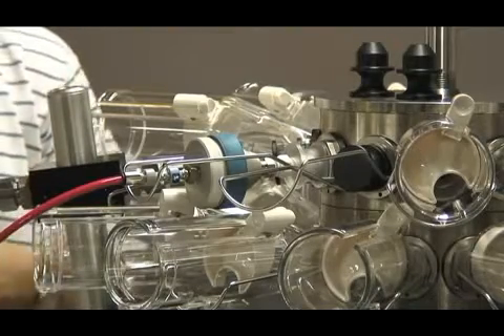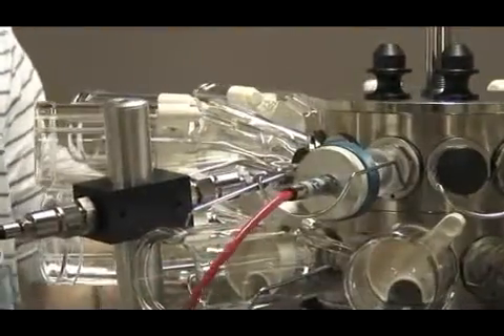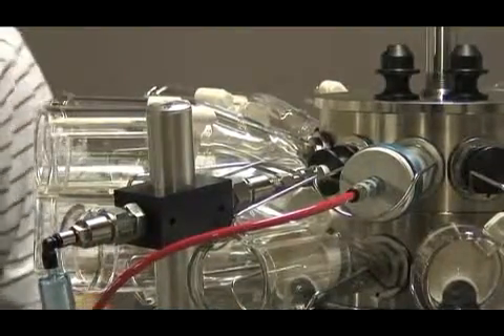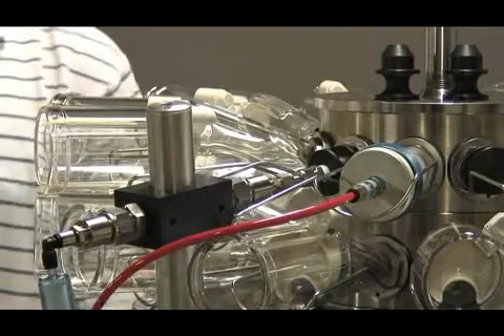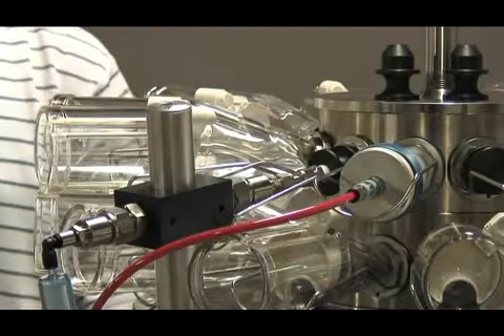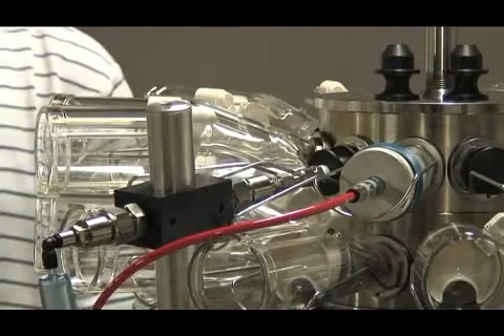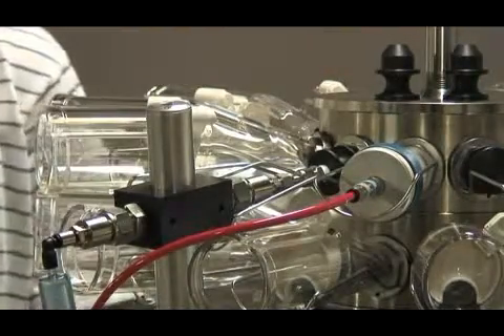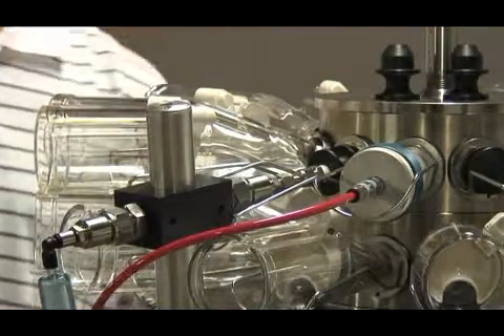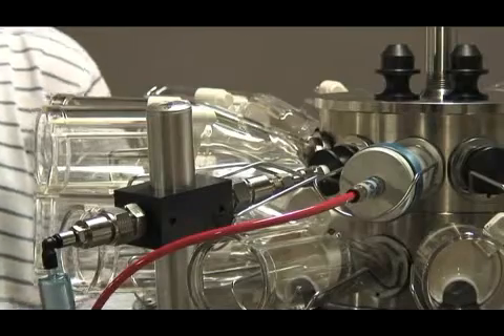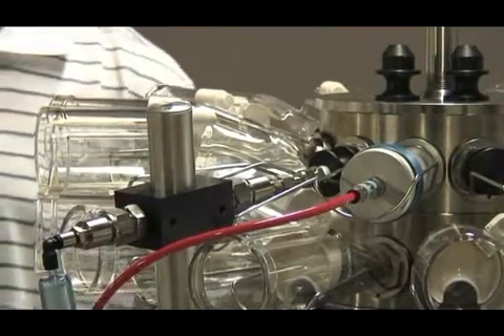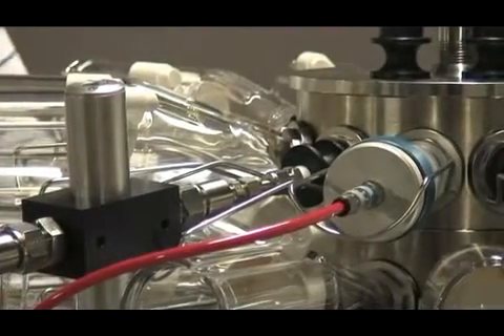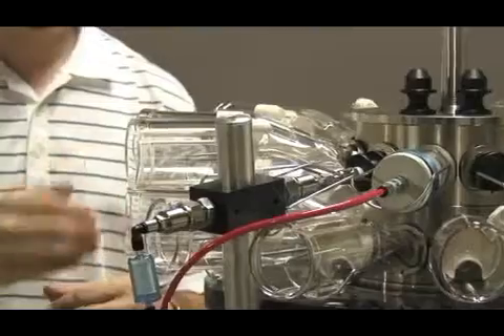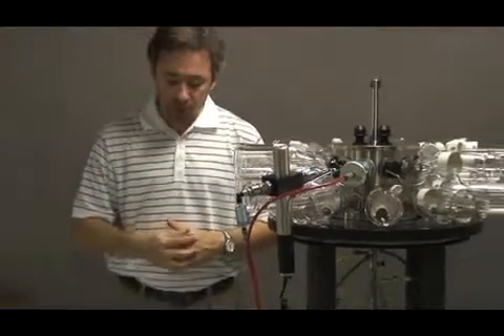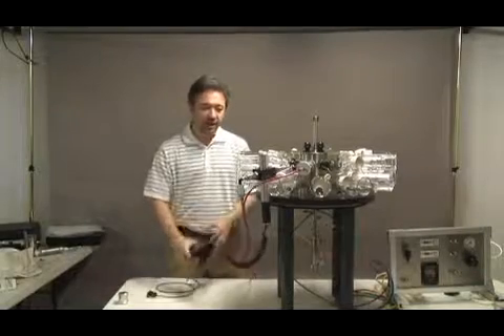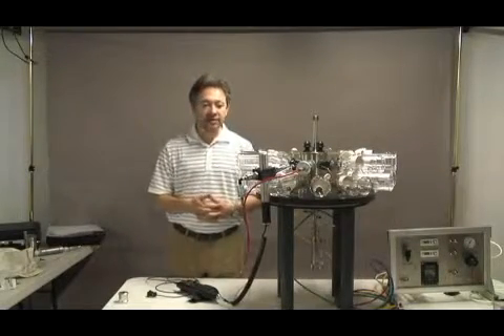So use a laboratory timer to measure the time, and let's say a 15 to 30 minute sampling period will be more than enough to have a good amount of aerosol on the filter. At the end, you will weigh the filter, you will calculate the concentration gravimetrically. We're going to give you a standard procedure for that. And in your computer, you will calculate the average of the readings of the probe, or you can read that directly from the screen, and then compare the two results.